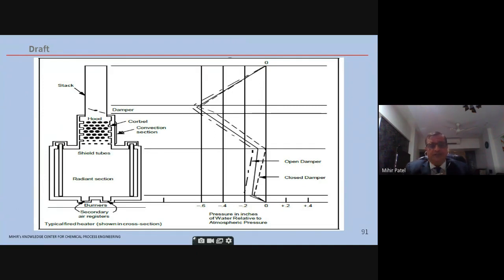So there are two things here. Suppose the casing has a leak. That means the flame is going to come out of that leak to the outside at a very hot temperature, maybe 700-750 degrees centigrade. If a person is standing there, he is going to expire on the spot. Second, if it is pressurized inside the firebox, the gases are going to permeate through the refractory and go to the casing, which, as I said, is construction grade steel, and it is going to cause corrosion there. This is not good because then again you have a negative aspect there.